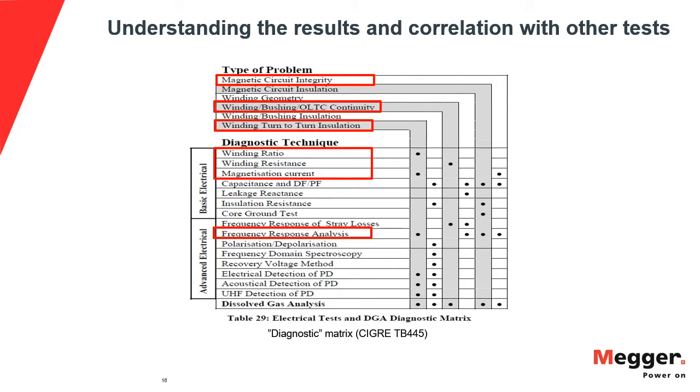We calculate the reciprocal of the magnitude in that part of the curve, and again, we can get a very good approximation of the TTR value. In other words, if we have a problem with TTR and we can also run an SFRA, we can use the tool to confirm an issue in that regard with our transformer.